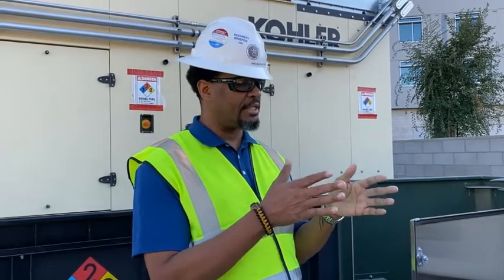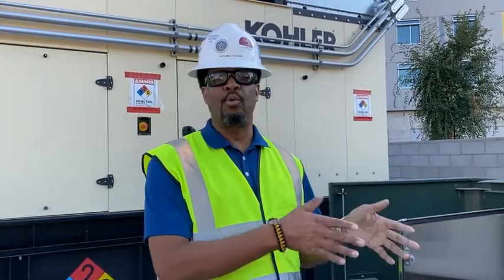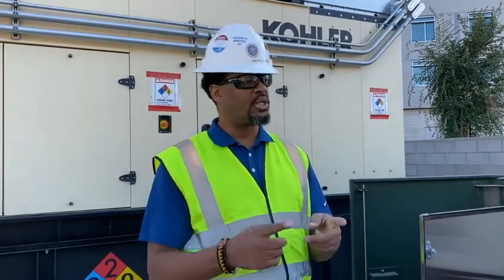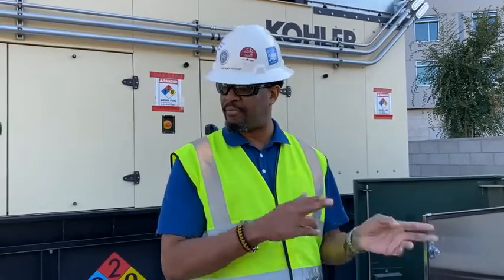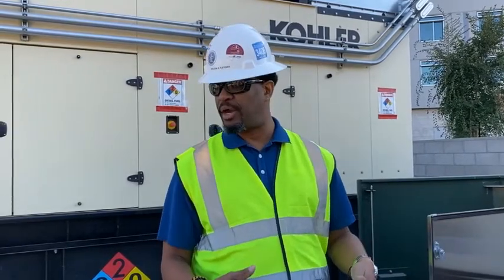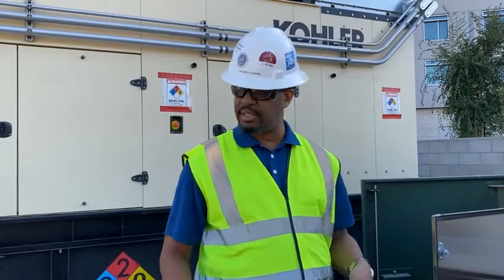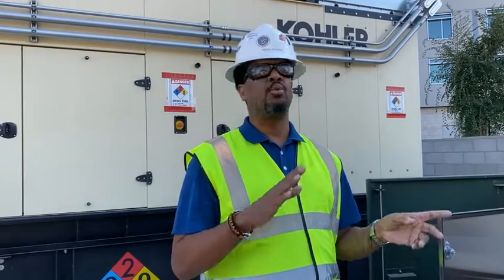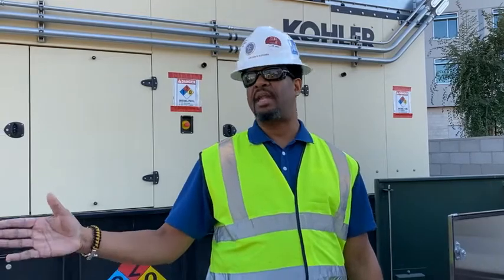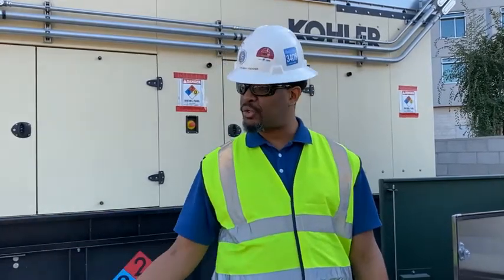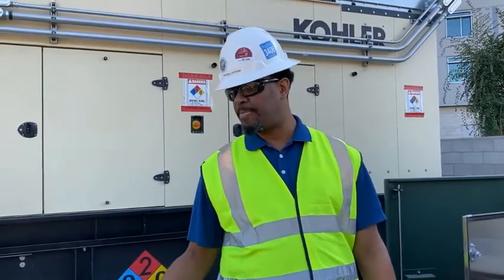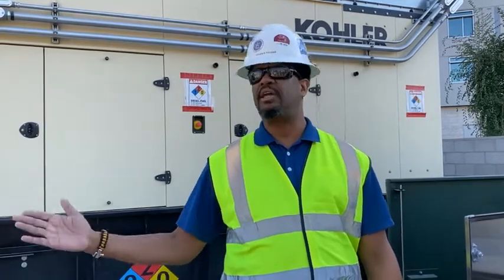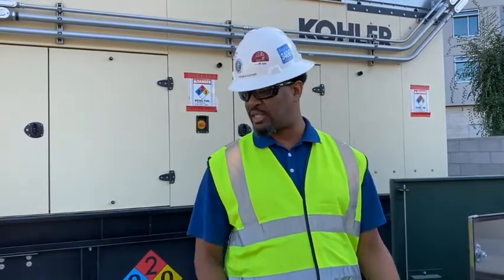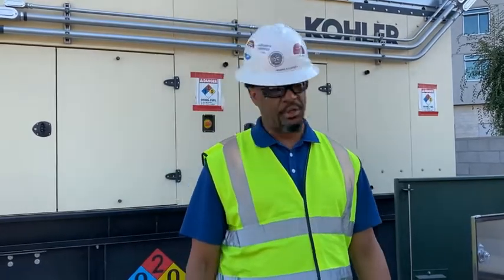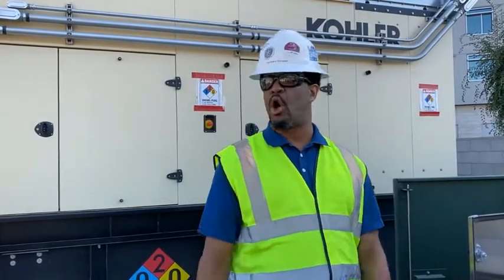So what you'll find is the individual that does the factory acceptance test will more than likely come out and do the site acceptance test. So once everything is in place, the same guy that did it in the factory will be out here, and he's got all the familiarity. If anything happens, the call comes into me, the call comes into the aftermarket group, and we'll definitely reach out to that individual. It may be something that he knew about that was being worked on, or something that he can fix pretty quickly. At the very least, he'll make his way out here and work with someone on site to correct the problem. So we're definitely going to stand behind it for as long as the system is in service.